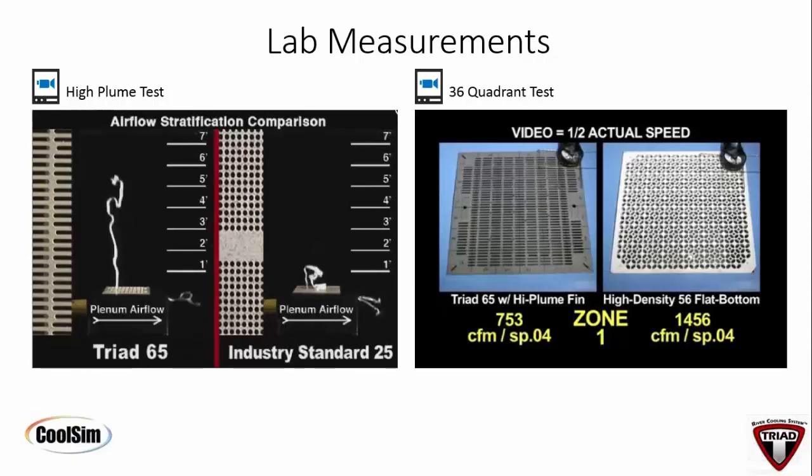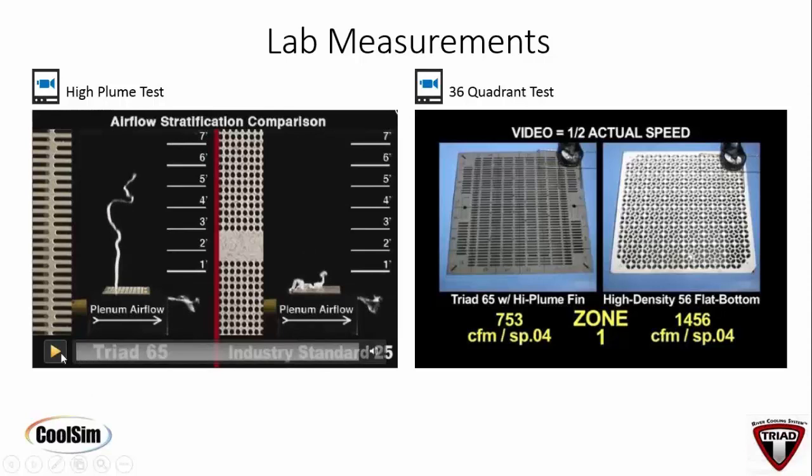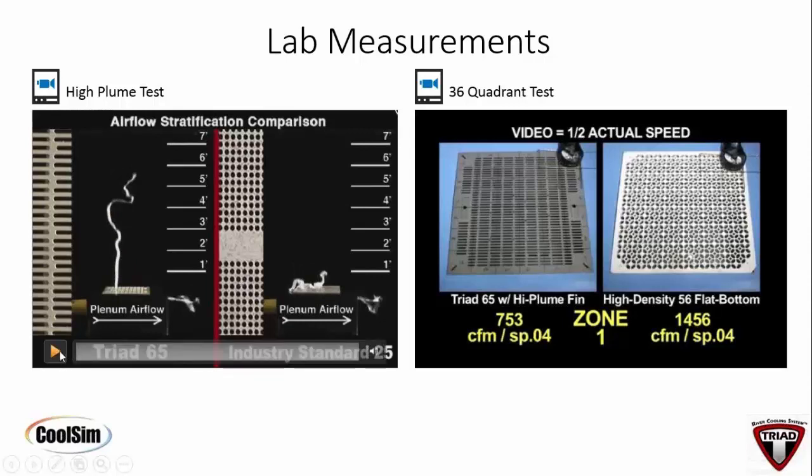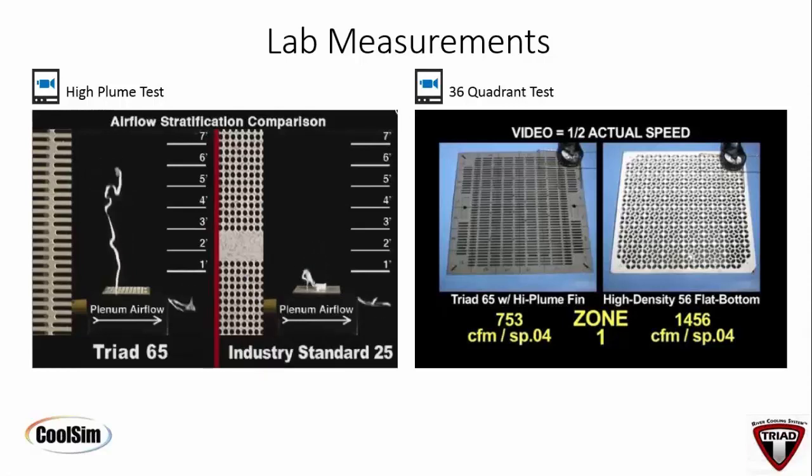And we could start to see that there were some dramatic differences in just the flow of the air out of the top surface of the airflow panel, even though everything else remained the same: the supply, the flow, the static pressure, all that was equal. There was a radical difference in how the air is dispersing, how it's stratifying coming out of the panels.